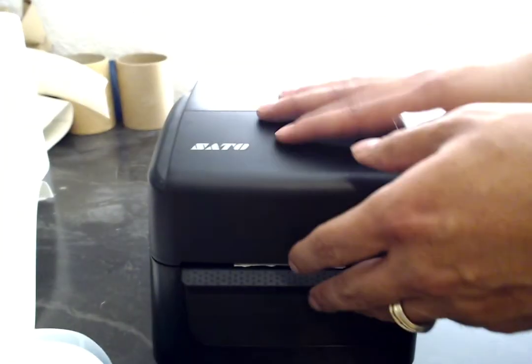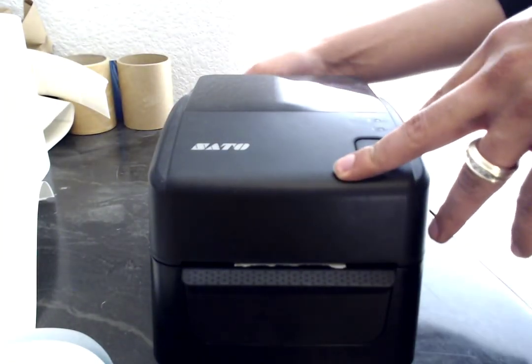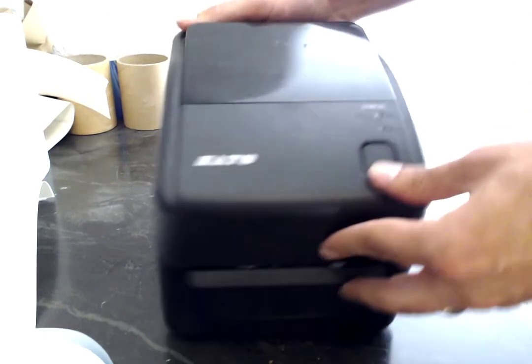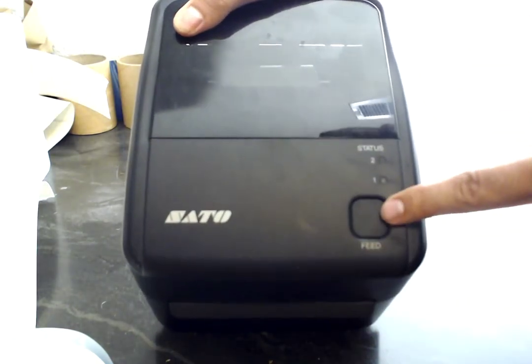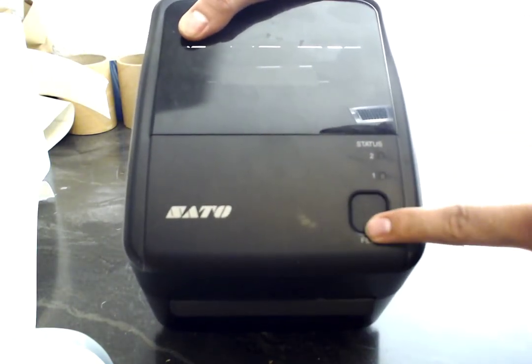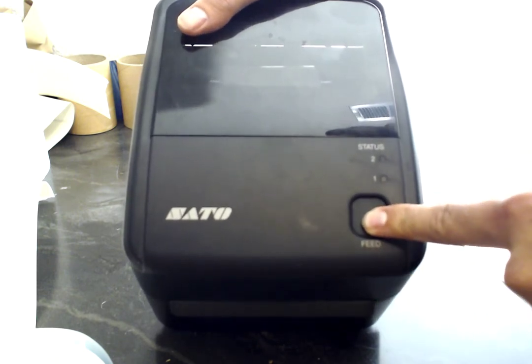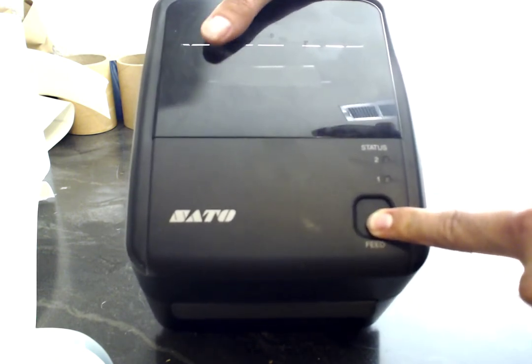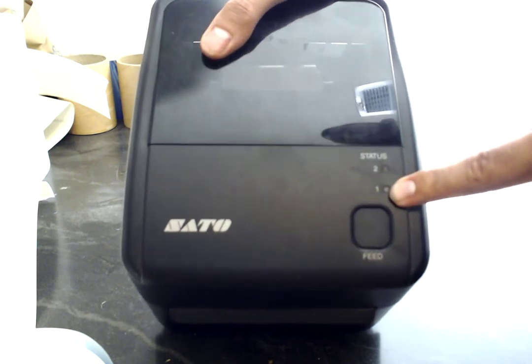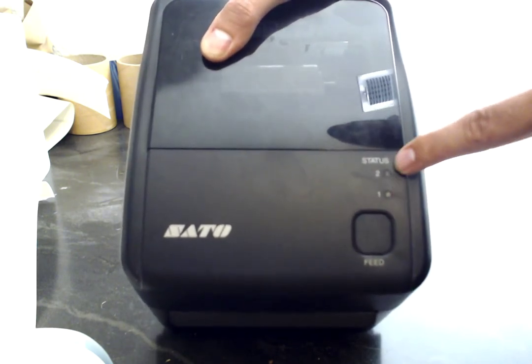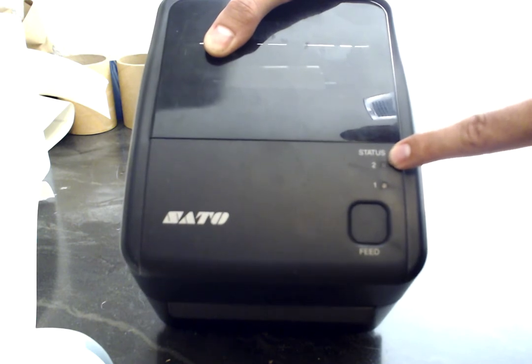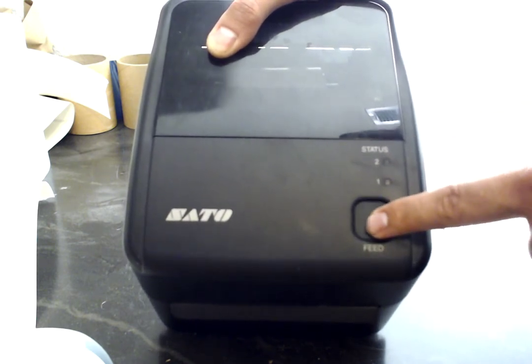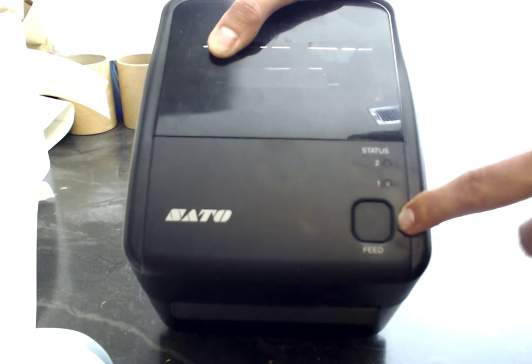Now we're going to turn off and close the printer module. Press the feed button right here before turning it on. Leave it pressed and then turn on the printer. Once we see that light number one is green and light number two is red, we let go of the feed button, press the feed button again, and the printer will calibrate itself.